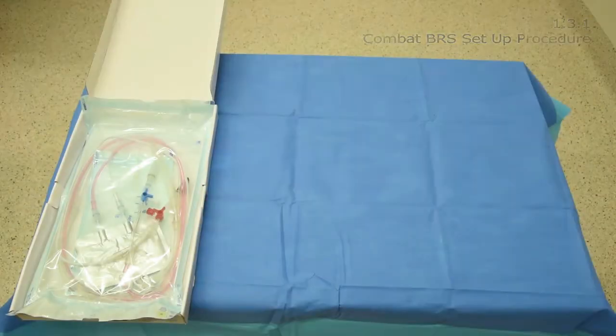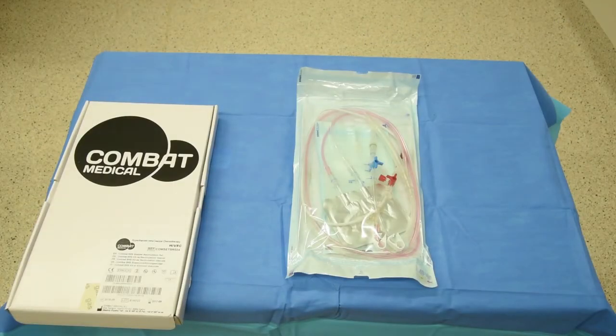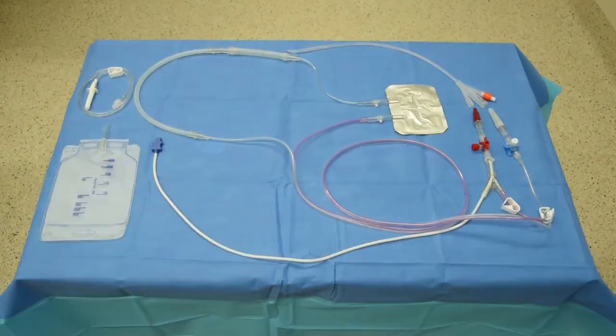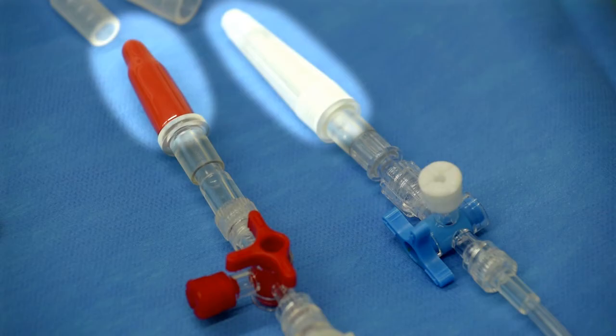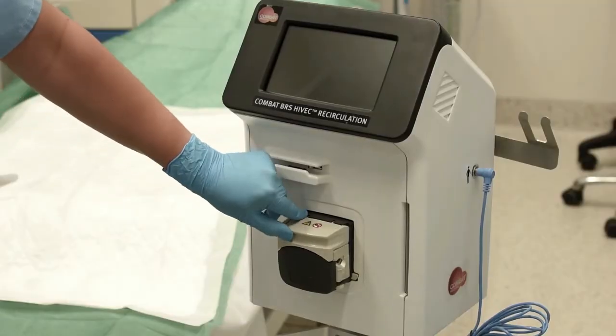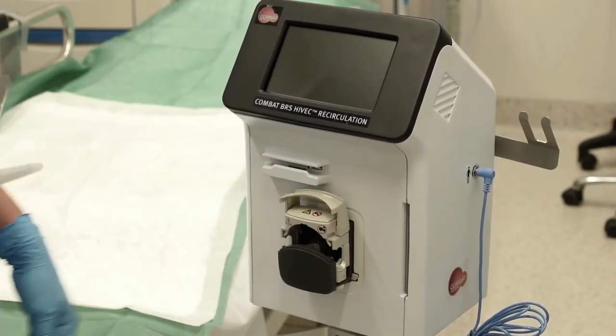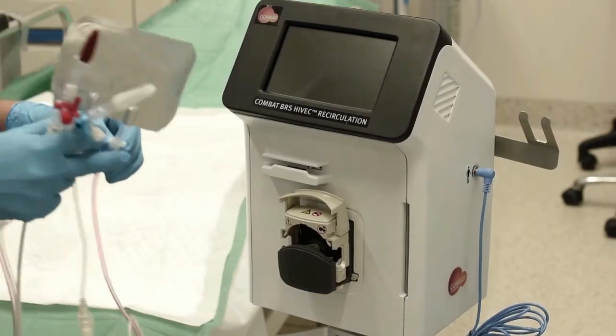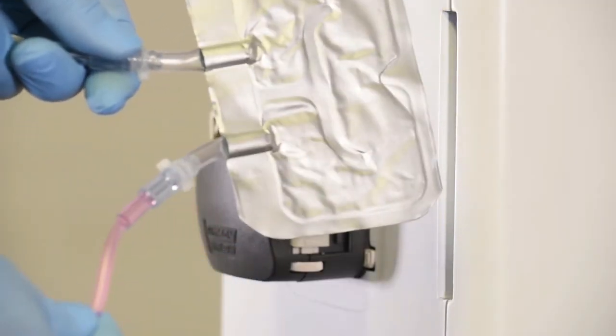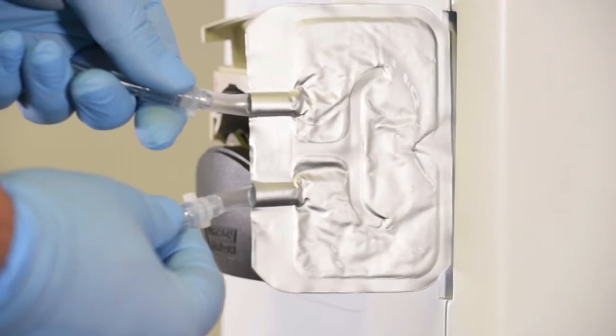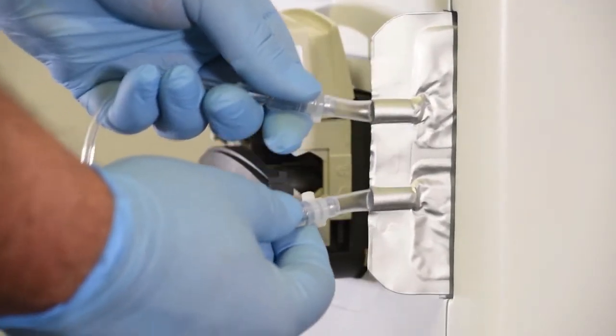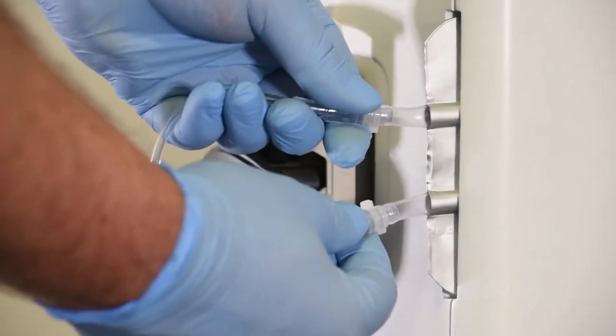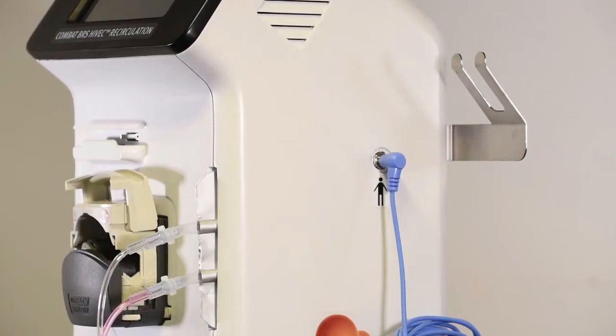Open the Combat Medical single-use disposable set pouch onto a sterile field and grasp the tubing of the giving set, leaving the caps in place. Open the pump cover of the peristaltic pump located on the front of the unit. Carefully insert the aluminium foil heat exchanger into the heating plate slot with the clear tubing uppermost and the red tubing below. Ensure that the heat exchanger is inserted as far as it will go.